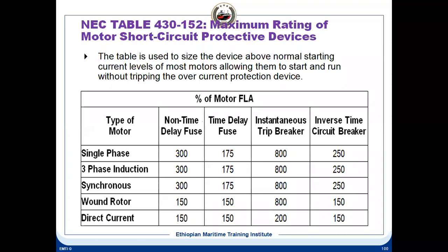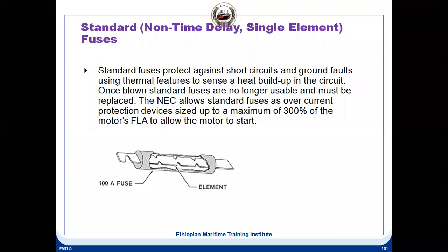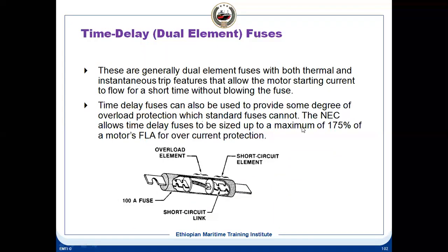So here, if you are using a non-time delay fuse for a 3-phase motor, that means it is up to 300%. That means the NEC allows a standard fuse overcurrent protection device size up to a maximum of 300% of the motor's full load current. So this is the non-time delay fuse. A standard fuse protects against short circuit and ground fault, using thermal features to sense a heat buildup.